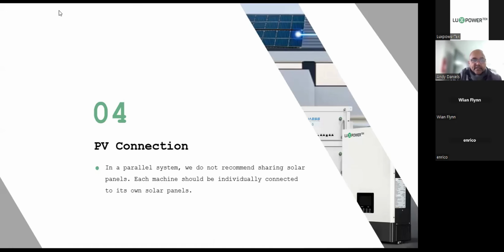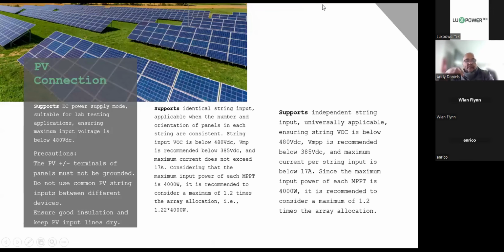PV connection. I'm going to have to spend some time here. All right, so as you know, when you set up your machine, you will notice that there are three input modes. The first input mode on your settings is DC source mode. Now, DC source mode is typically used by us in the lab or for testing, where we have a stable or flat supply of power coming in on the DC. So the system doesn't have to do any tracking. When we do testing in the lab or at the R&D facility, they will normally set it to DC power supply because it's a stable or flat line of DC coming in. That's the only time you will use that.